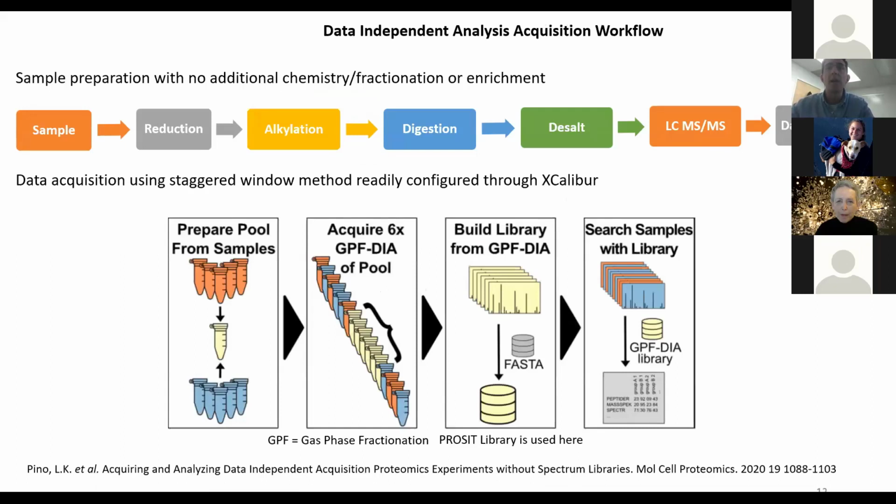So we're going back now to our evolved pipeline. And we're taking a method from the literature and bringing it into our lab and reproducing it with no other changes beyond instrument settings and data processing. So we were very excited to do this. Xcalibur now running on Windows 10. It has data acquisition options in there that can be configured with reference to the literature. It's very easy to bring this on board.